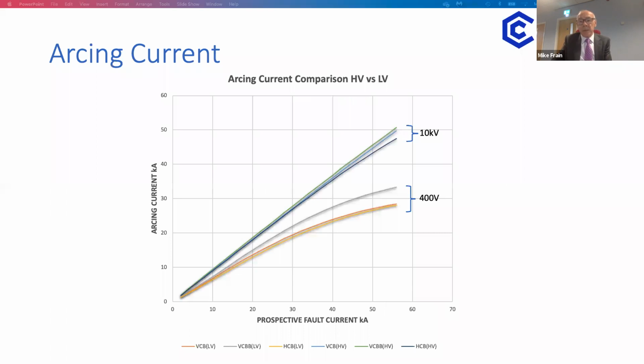The first thing that the calculations will tell you is the value of arcing current. It'll not come as much of a surprise to find that the arcing current will be lower than the available prospective short circuit current because of the impedance. At high voltage, this attenuation is very much less than at low voltage. You can see that in this graph, which shows arcing current against prospective short circuit current for 3 different electrode configurations. Firstly, for a 10 kV system, which is at the top of the graph, the straighter lines, and then lower down is for a 400 volt system voltage. While you're extremely unlikely to experience fault levels of 50,000 amps at 10 or 11 kV, the graph just serves to make a comparison, that's all.